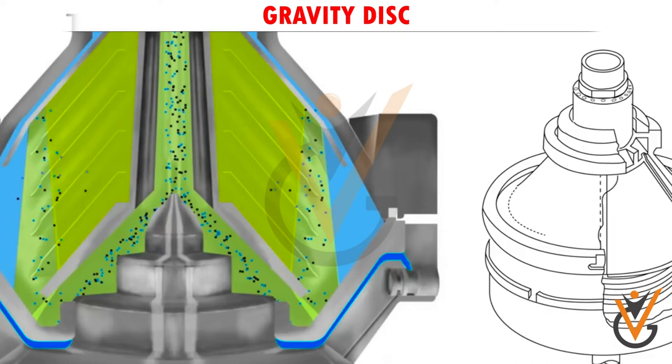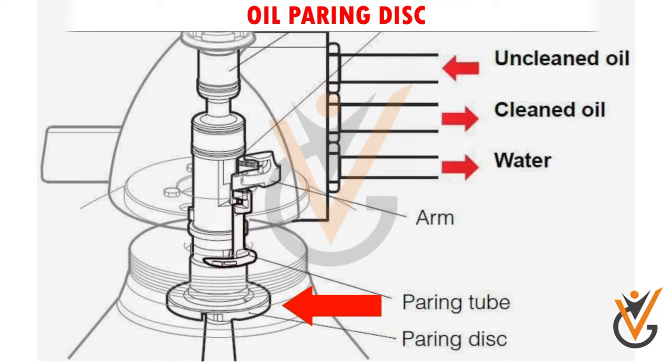Gravity disc: The main component of purifier is correct size gravity disc or dam ring which is responsible for maintaining an interface between oil and water. Gravity disc is fitted at the heavy phase outlet, water outlet.